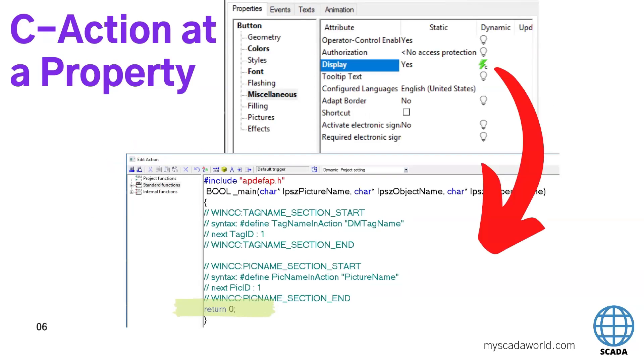In the graphic designer, we can put C actions at the property level. We can see on screen a button, we can see the property 'display', and we can put a C action inside this. We go to right-click, C action, and we see the editor window below. This kind of action needs to return any value — so if you want to make a property, you need to always return something. If we want to change the display property, we need to return display or not display.